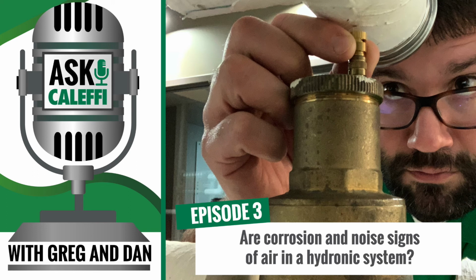Our all brass ones, from the 1-inch on up to the 2-inch in the 551 series, you can remove just the vent cap and float, or you can take the entire vent off and access the coalescing mesh. You can pull that coalescing mesh right out and clean it, inspect the body, and reassemble the whole thing and you're back in business again.